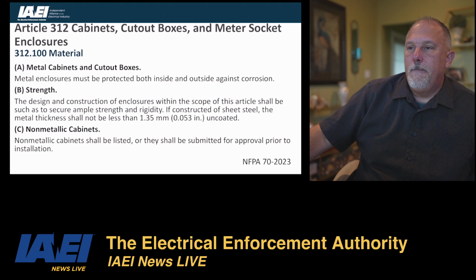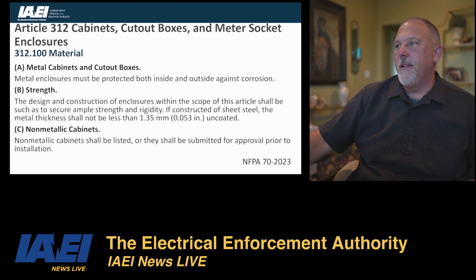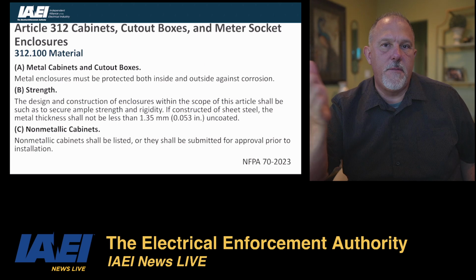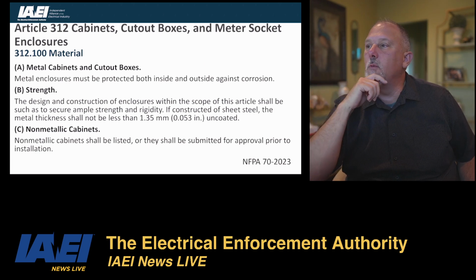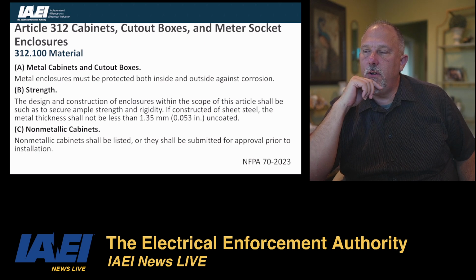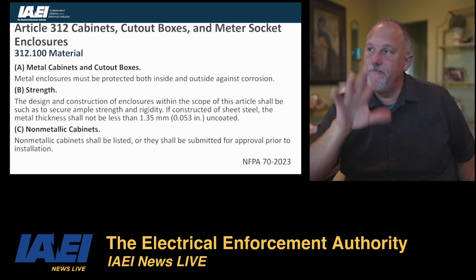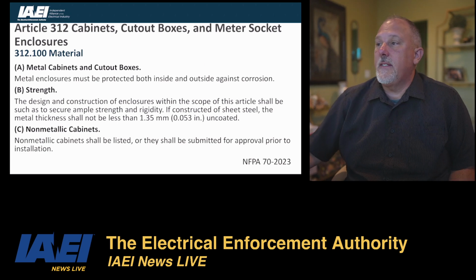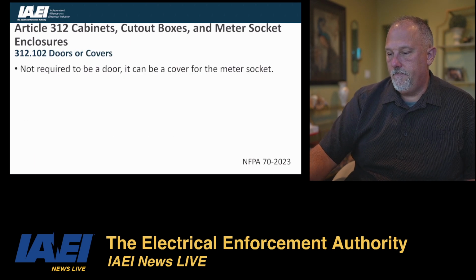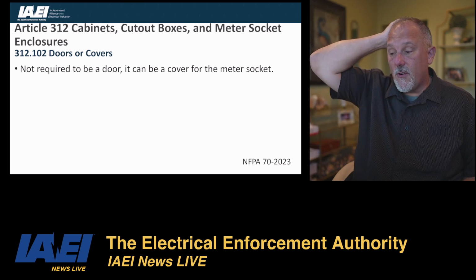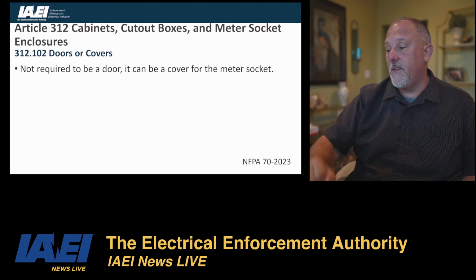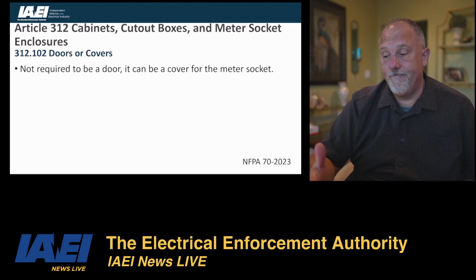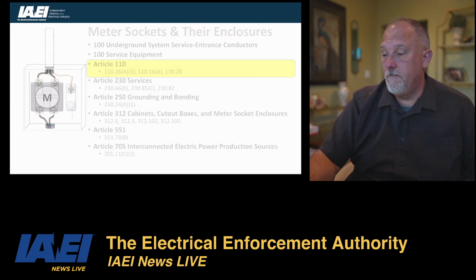All right. Just looking to see in Article 230, they should have moved everything listing. It says all service equipment shall be listed or field evaluated. And when they do a field evaluation by a field evaluation body, they're going to mark it anyway. So all service equipment has to be listed. Now that is, again, which falls under the purview of the NEC. All right. 312.102, doors or covers, not required to be a door, but it can be just a cover, like a bolt-on cover for the meter socket, etc. But remember, if it's listed, you're good to go.